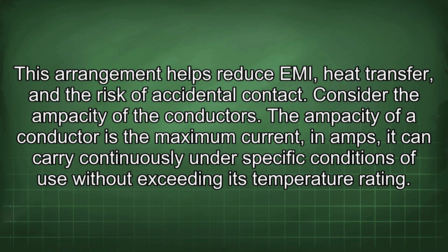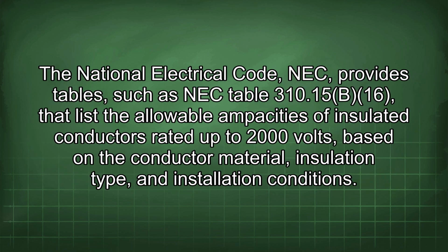Consider the ampacity of the conductors. The ampacity of a conductor is the maximum current, in amps, it can carry continuously under specific conditions of use without exceeding its temperature rating. The National Electrical Code (NEC) provides tables, such as NEC Table 310.15(B)(16), that list the allowable ampacities of insulated conductors rated up to 2000 volts, based on the conductor material, insulation type, and installation conditions.